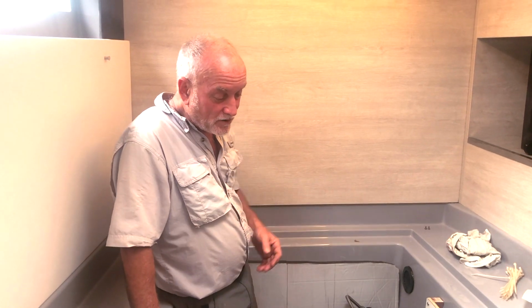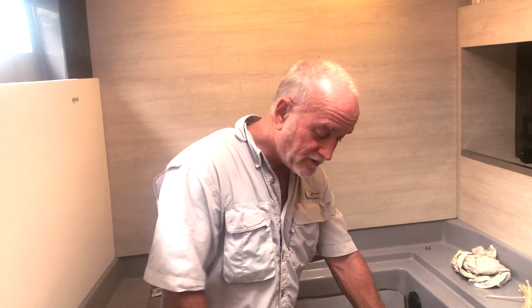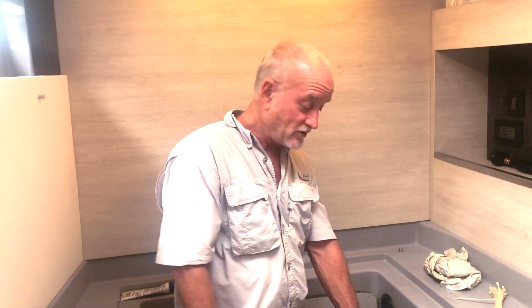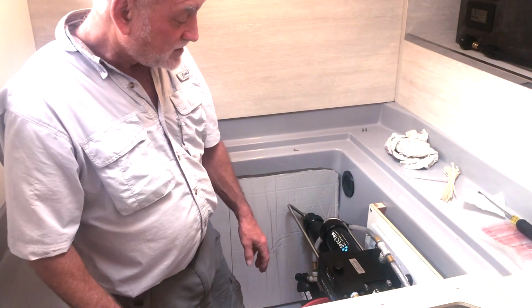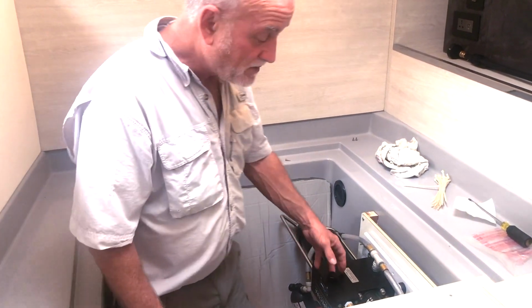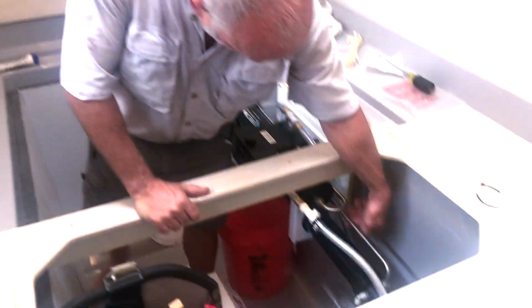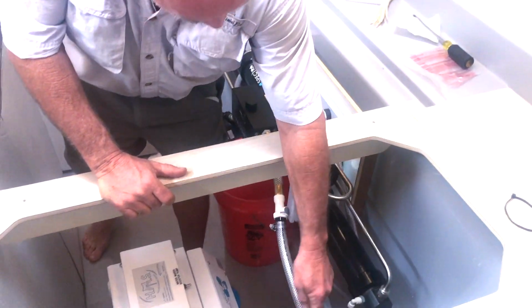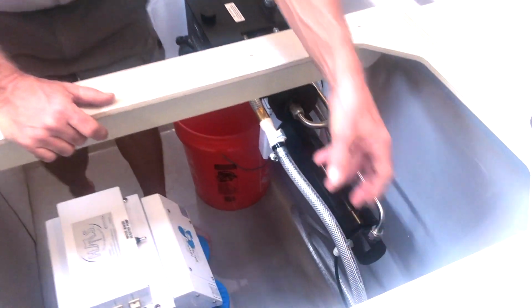So it's going to bump the pressure up to about 650 pounds directly. And there are no electrical moving parts in this. It's only driven by the hydraulic pressure created by the feed pump. So there's no electrical use here. It bumps that pressure up to about 650 pounds. It's going to send all of that right to the end of the membrane, where the brine seal side is, passing that through there.